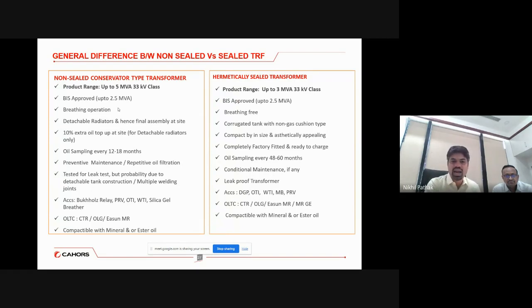So just to add a comparative statement, the product line of non-sealed is available up to 5 MVA and sealed up to 3 MVA. This goes in the breathing operation. Breathing means whenever the pressure goes down, the air is sucked in by the transformer, and when the pressure is released with the oil, and naturally the loading of the transformer and heat of the oil, the air is released from the transformer. So that is how the breathing operation happens in a conventional transformer.